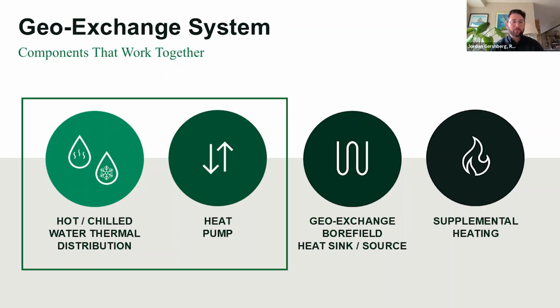It's coupling a thermal utility, pushing around hot water and chilled water in pipes, and connecting that to a side of a heat pump. That alone is capable of generating the thermal utilities we want. However, we want more energy efficiency and the ability to decouple the instantaneous needs of the heating and cooling systems, so we would connect a Geo-Exchange bore field as a heat source or heat sink.